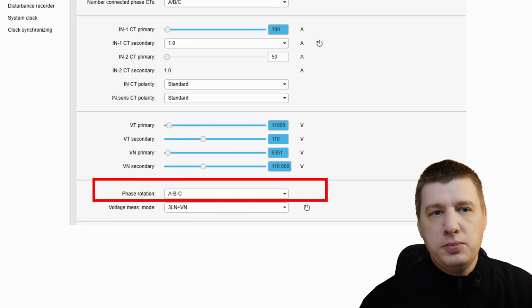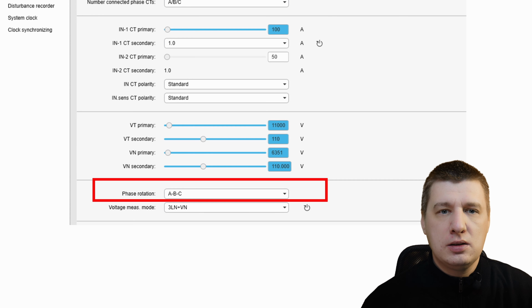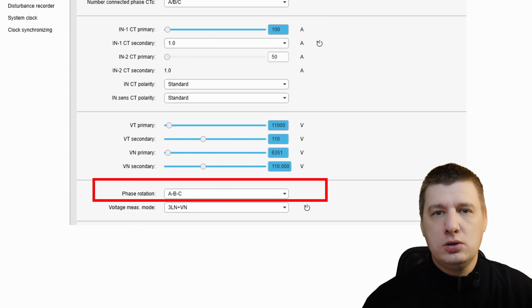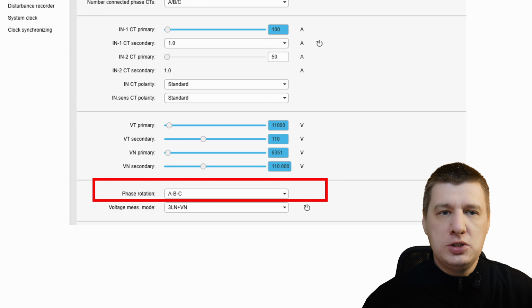When you're setting up your P5 relay, you will encounter the phase rotation setting. You can choose from 1-2-3 or 1-3-2, which corresponds to the more common labels ABC or ACB. It might seem like a small detail, but getting this wrong will make your directional protection and negative sequence readings completely incorrect. ABC or standard rotation means that your phase voltage and current reach their peak values in the specific order: phase 1, then phase 2, and finally phase 3. In the P5, this is the default setting.